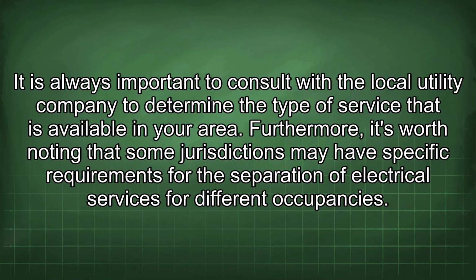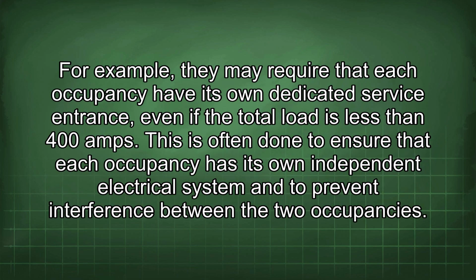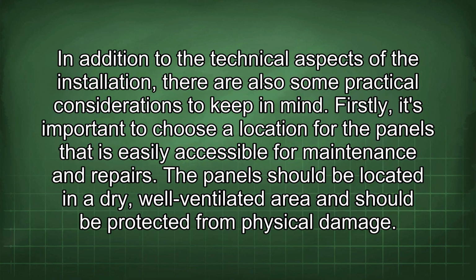in your area. Furthermore, it's worth noting that some jurisdictions may have specific requirements for the separation of electrical services for different occupancies. For example, they may require that each occupancy have its own dedicated service entrance, even if the total load is less than 400 amps. This is often done to ensure that each occupancy has its own independent electrical system and to prevent interference between the two occupancies.